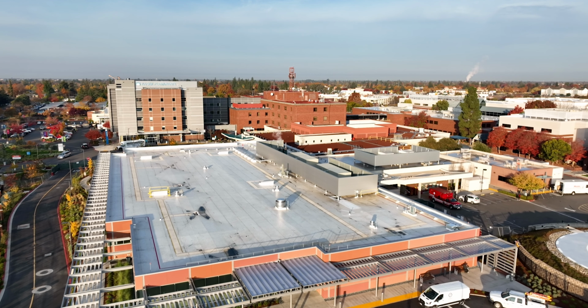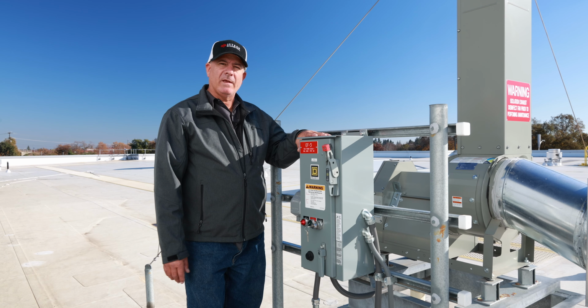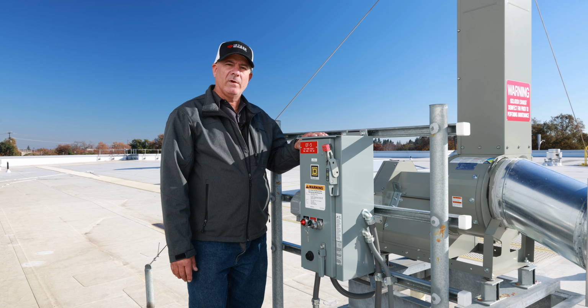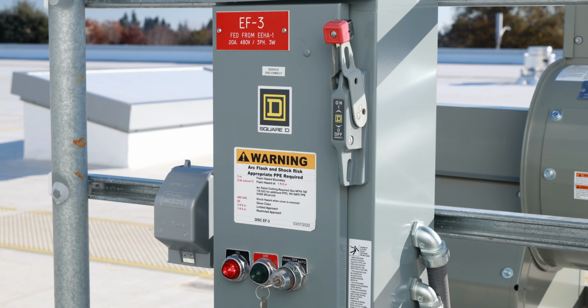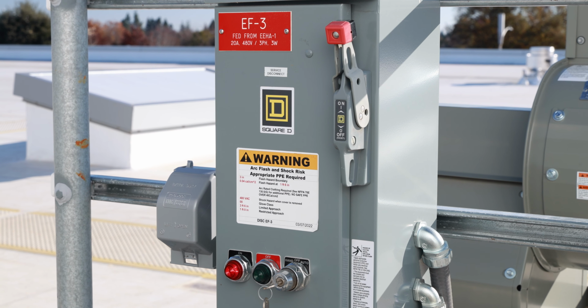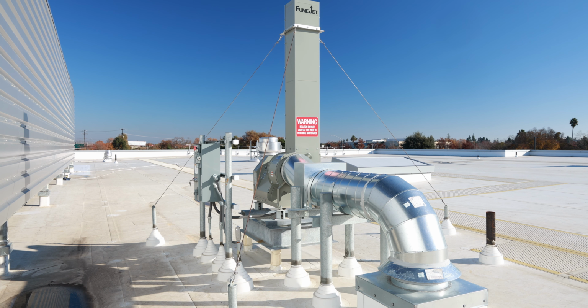On the roof, we have 7 exhaust fans. This is exhaust fan 3. It's the only one on the roof with a starter. It does have a HOA. It's a belt-driven fan, so it will be a maintainable item.